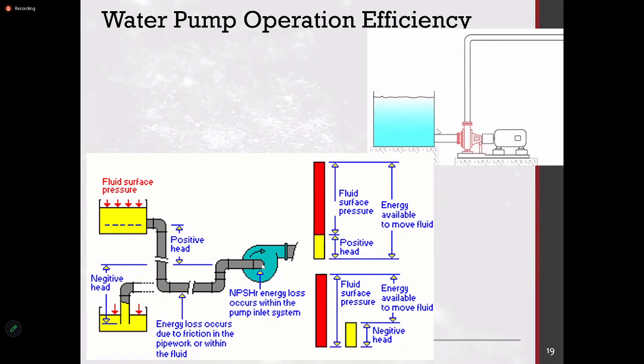So fire pumps essentially these days have to be this type of arrangement, where you have to take the pump to the bottom of the sump. So these are actually costly constructions, where you have to have a separate underground pump room kind of a thing, to ensure that the same level is maintained. So in this type of arrangement, the pipes will not run dry, or the pump will not run dry.